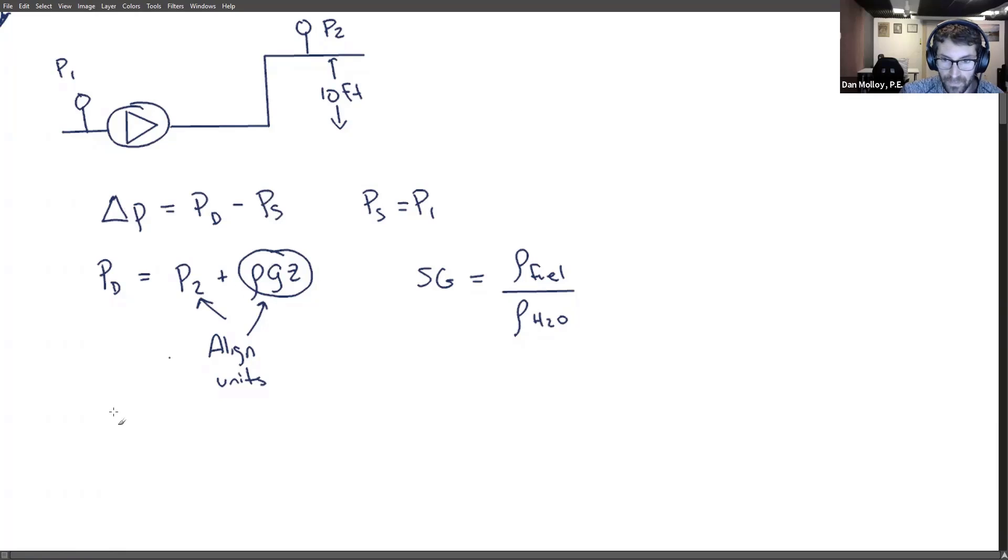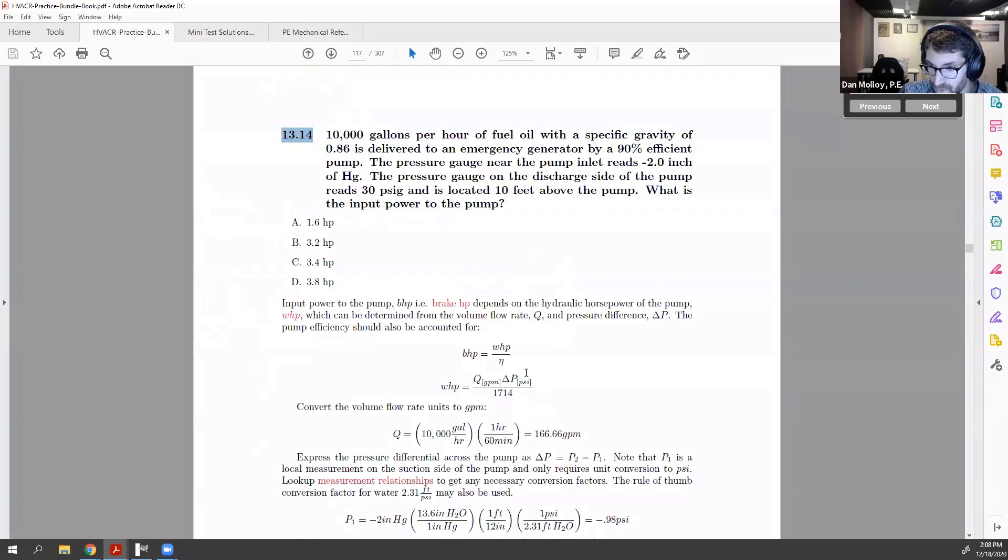Then and only then can I add to P2, I can get the discharge pressure, and ultimately you'll get the delta P in psi. When you do that, you're allowed to use the formula WHP equals Q in GPM times delta P in psi over 1714. That formula, and that's the formula that I used in my solution here.